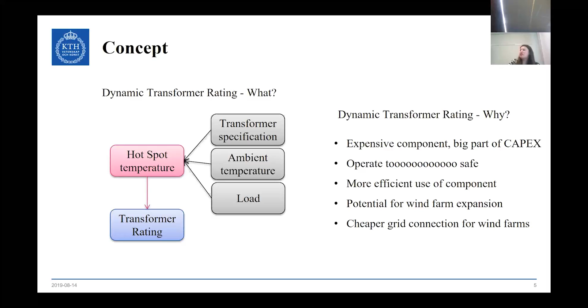What we did with dynamic transformer rating: we ran our first study several years ago. We used a transformer connected to a wind farm and analyzed its performance. We had the yearly load and temperature data, temperature from the transformer oil, as well as ambient temperature data provided by the Swedish DSO. After thorough calculations with the help of our partners at ABB, we determined that insulation life expectancy is very high, almost 20,000 years.